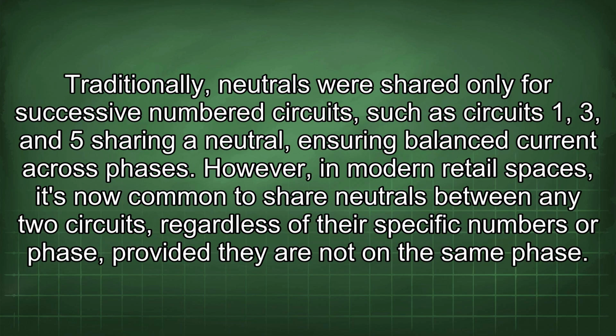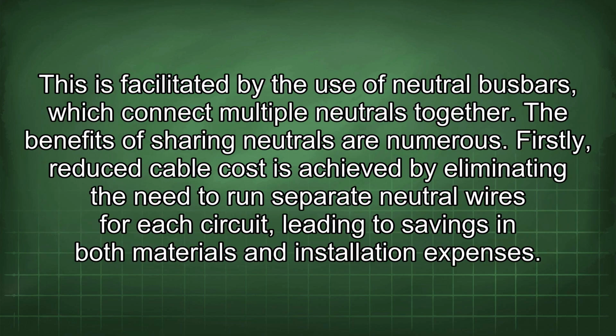Traditionally, neutrals were shared only for successive numbered circuits, such as circuits 1, 3, and 5 sharing a neutral, ensuring balanced current across phases. However, in modern retail spaces, it's now common to share neutrals between any two circuits, regardless of their specific numbers or phase, provided they are not on the same phase. This is facilitated by the use of neutral busbars, which connect multiple neutrals together.